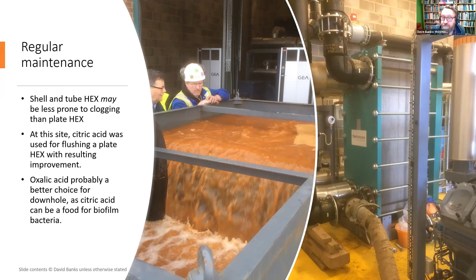You can see all the gunk that's being washed out of the heat exchanger. Word of caution, don't use citric acid in boreholes. Oxalic acid is a better choice because the citric acid can be a food for bacteria. We've also found at several sites in the UK and on the continent that shell and tube heat exchangers tend to be a little bit less prone to clogging than plate heat exchangers, but they're a lot bigger and possibly a bit more expensive.